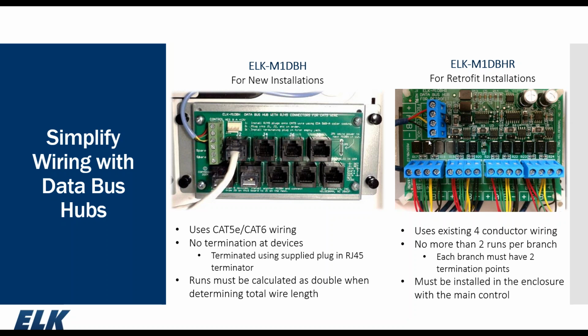This is an active device. There's a tremendous amount of information being transferred from each branch back to the M1. So it is very important to make sure that the distance from the input here to the M1 is as short as possible, making sure it's in the same enclosure. And you can have up to 2 of the retrofit hubs in parallel with each other. Like I said, this is an active device, a lot of information being transferred. We keep that distance as short as possible. You can have 2 home runs per branch, properly terminating each branch using the included jumper.